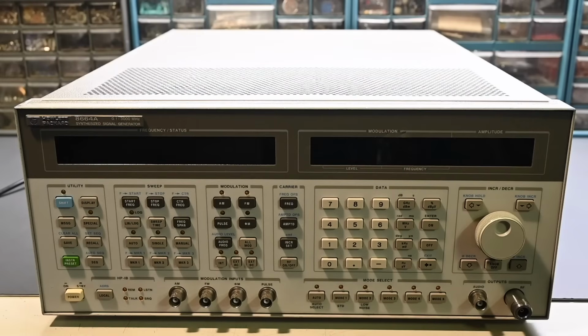Now, the manual mentions that an ALC out of lock error can occur in certain situations and not necessarily be a hardware failure. The memory lost error could be a dead battery, and this uses an internal NiCad battery. I think it should be inspected and possibly replaced given the age of the instrument. It may have been replaced previously, but I have no history about this instrument, so we'll definitely want to inspect that NiCad battery. If the battery is completely dried out and not working, it's never going to hold a charge. But the whole purpose of the NiCad battery is to hold up the memory.